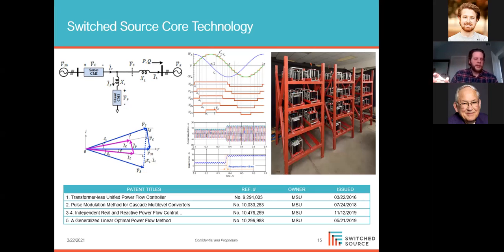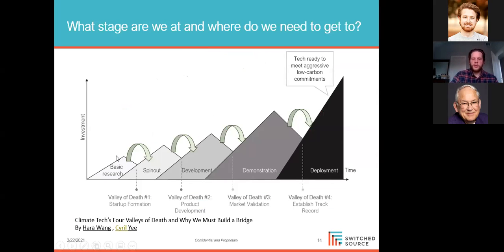So there's some elegance there, but what you're trading off is having to deal with a lot of different modules, a lot of communications to those modules, and a bunch of problems around creating a utility-grade version of this device with all the isolation needed for creepage and clearance distances, plus the BIL ratings your device will require. There's a lot of baggage that's just table stakes to get equipment in the ground with a distribution utility, which isn't necessarily considered during the basic research stage.